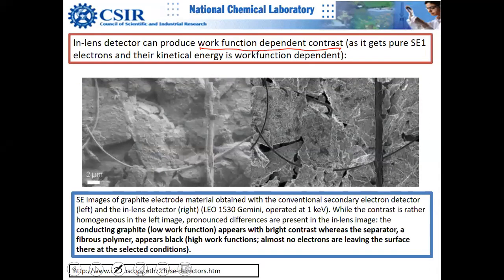The energy of secondary electrons will vary based on the work function. Previously this was not possible due to interference from SE2, SE3, SE4, and from the bias voltage which destroys subtle information. Surface charge can also destroy work function contrast, so the sample must be well-grounded to preserve it.